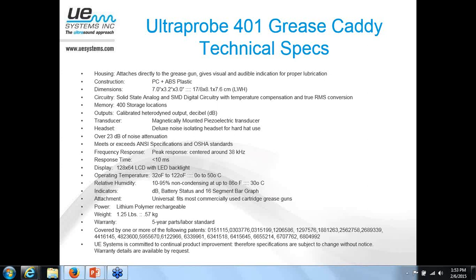Yep. Okay, so back to the slow speed bearing, someone chimed in. I guess we got people thinking about it. Is there a size limit when it comes to slow speed bearings? In other words, is this practical with smaller slow speed bearings like those on a conveyor belt? No, the size of the bearing doesn't have any effect on the ultrasound. What will happen is when you get into some of those slower speed bearings, if that bearing is good, it may not even register a dB, just because there's nothing in there creating any kind of noise.